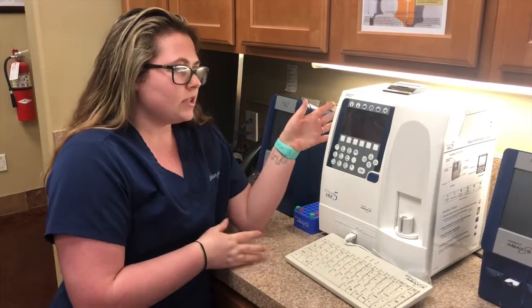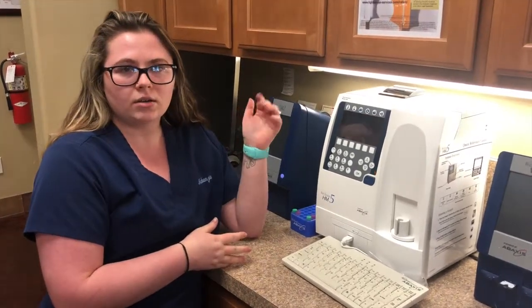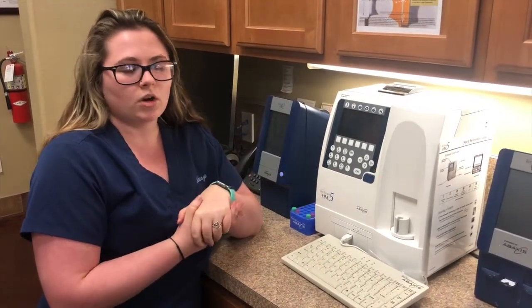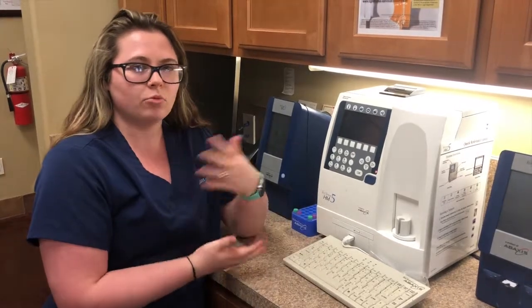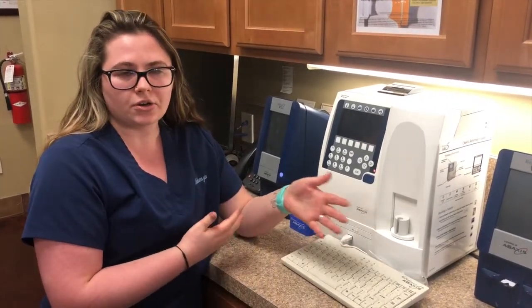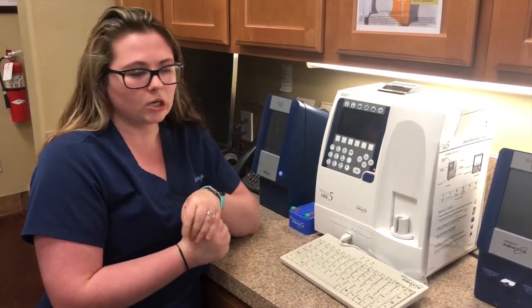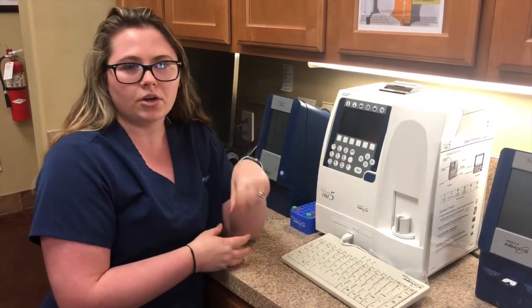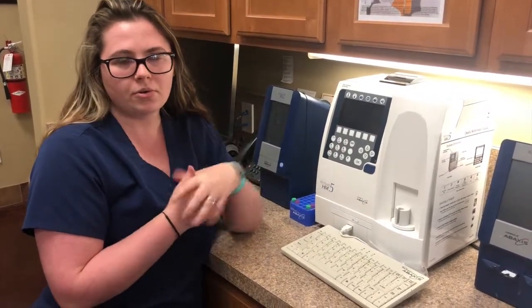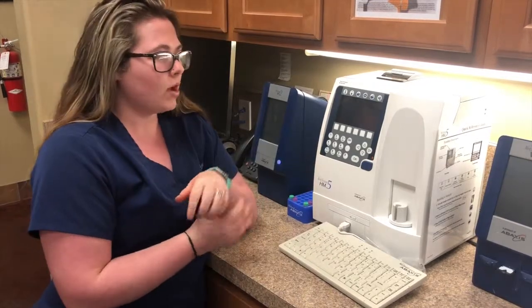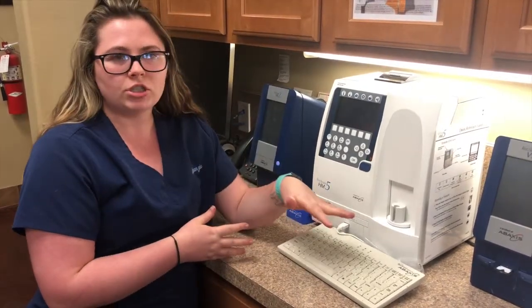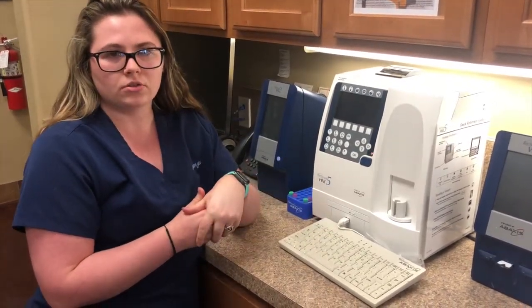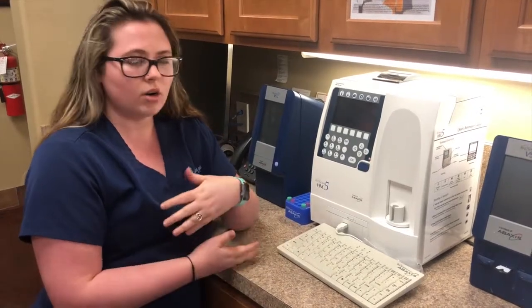The machine will ask you to do an enzymatic cleaner monthly or as needed. So the more tests you run, about every 100 tests or so, it will ask you to run your enzymatic cleaner. That's this cleaner that we have that we put in our EDTA or our purple top tube, and you put about 0.3 mils in it and run that, and that just makes sure the machine is running properly and all your test results are what you need them to be and running normally.